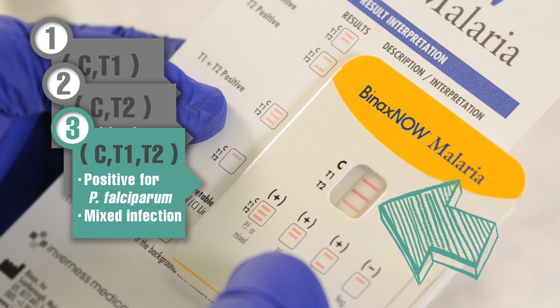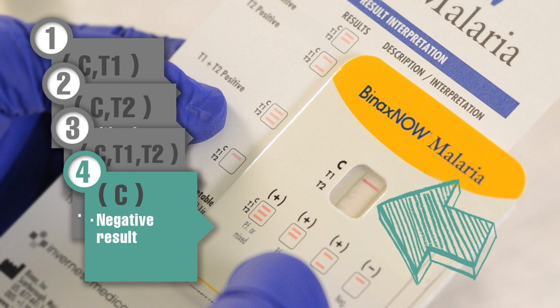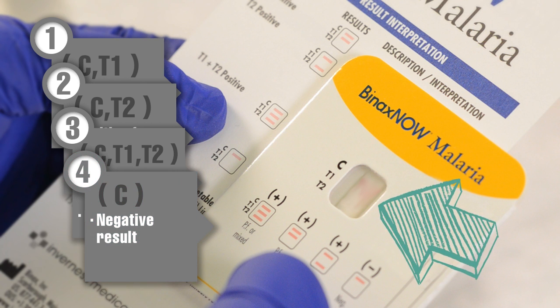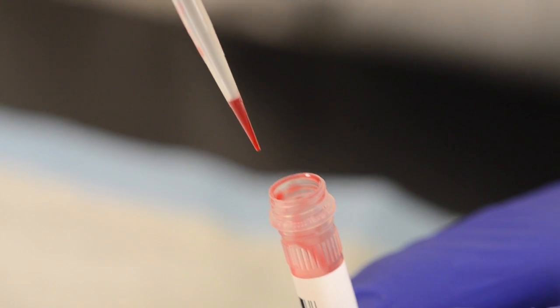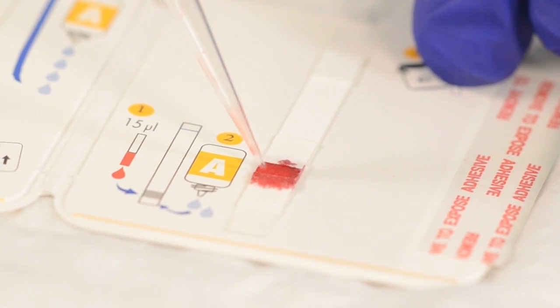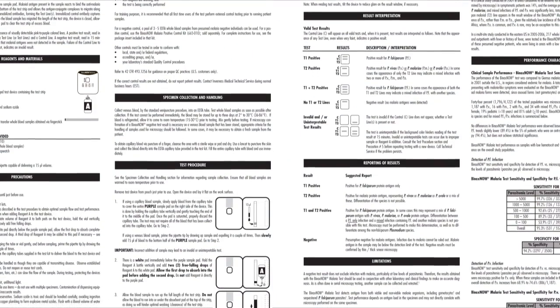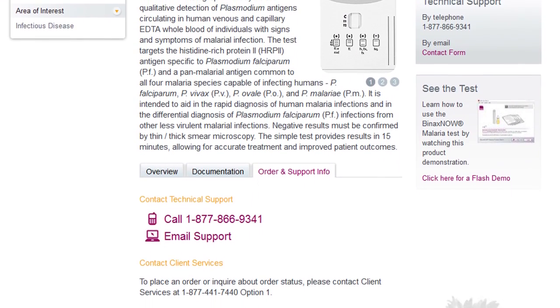If no T1 or T2 lines are visible, this indicates a negative result. If the background color hinders reading of the test result at 15 minutes, the test is uninterpretable and should be considered invalid. Invalid or uninterpretable tests can occur due to improper sample or reagent application. Consult the package insert or bench aid before testing with a new device. Call technical services at the number indicated on the insert if the problem persists.